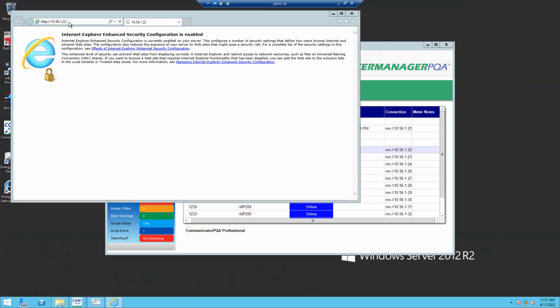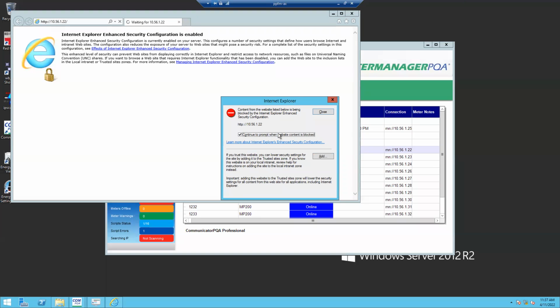And the web pages are handy for the BMS guys if they're setting up a meter and they just want to confirm the readings from the meter to what the BMS is, make sure it's scaled correctly and that kind of thing. You can just compare it.